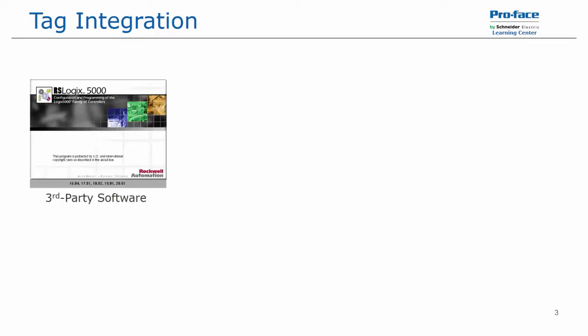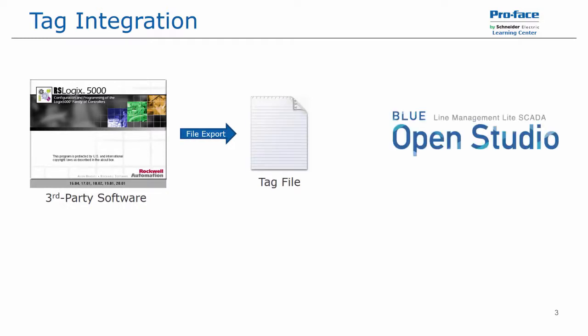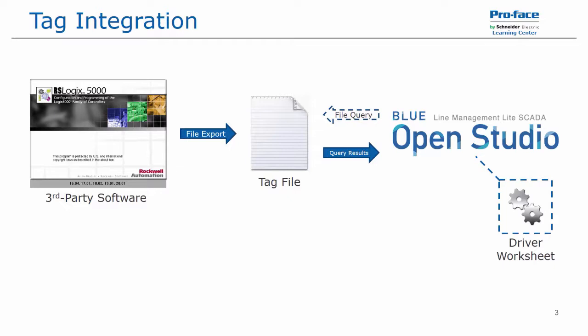Using tag integration in Blue Open Studio, you can point to a pre-existing PLC tag file and have access to those tags. You are not actually importing the tag list into the application, but you are querying the tag file and selecting the specific tags you want to use. Additionally, when tags are selected or referenced in the application, a driver worksheet is created automatically.